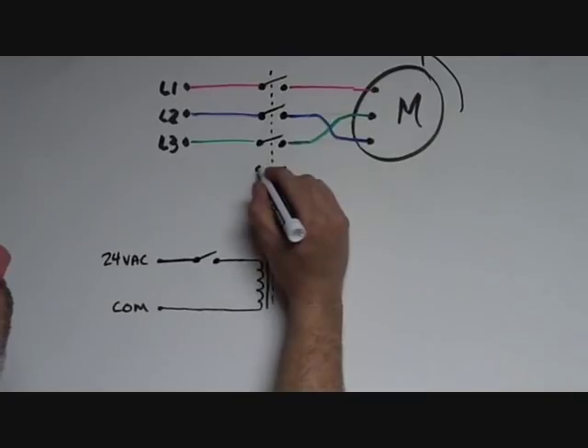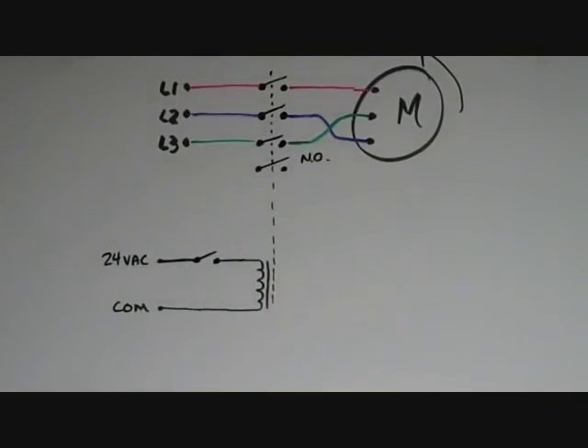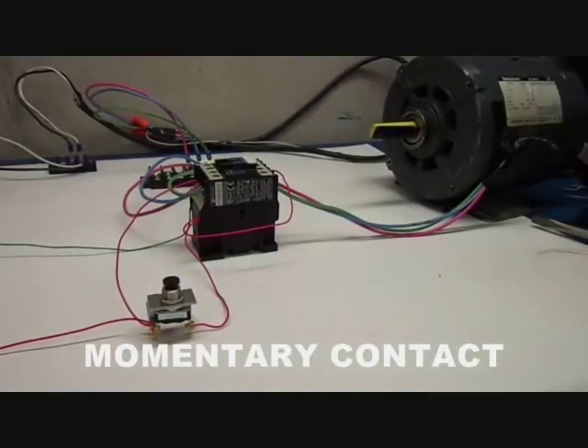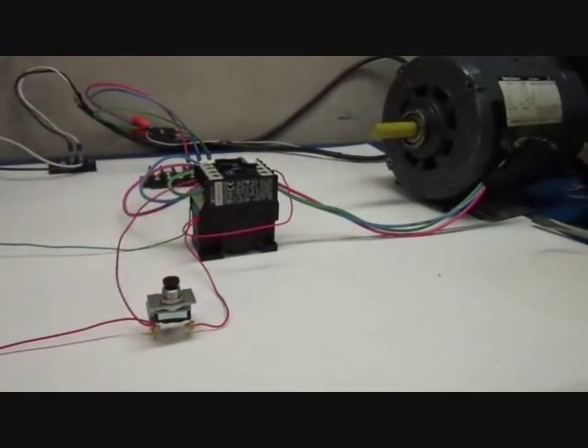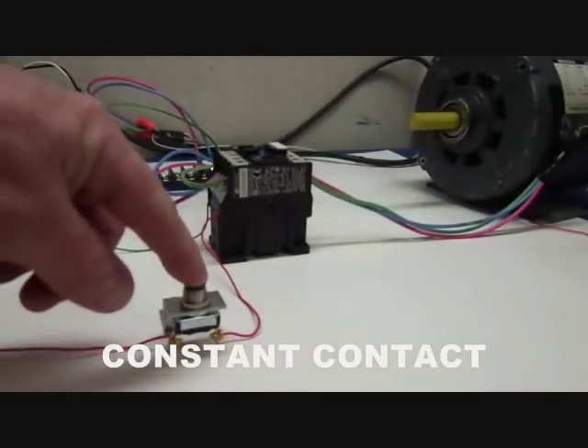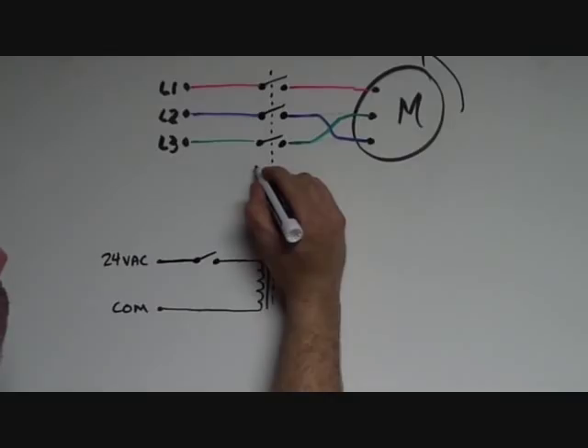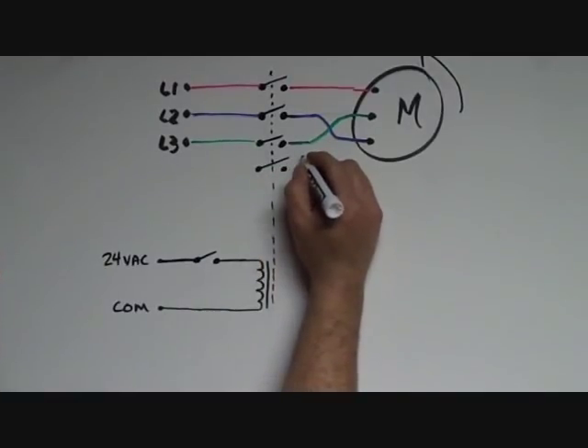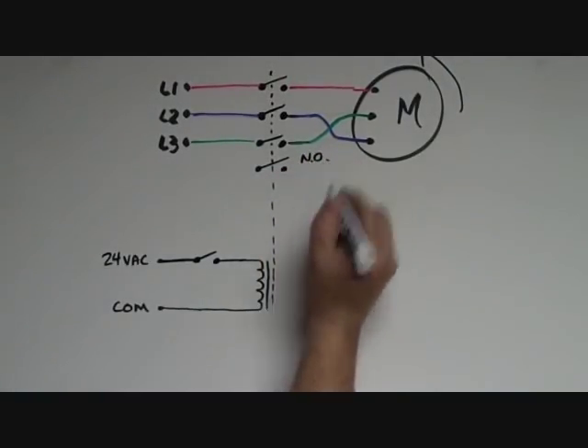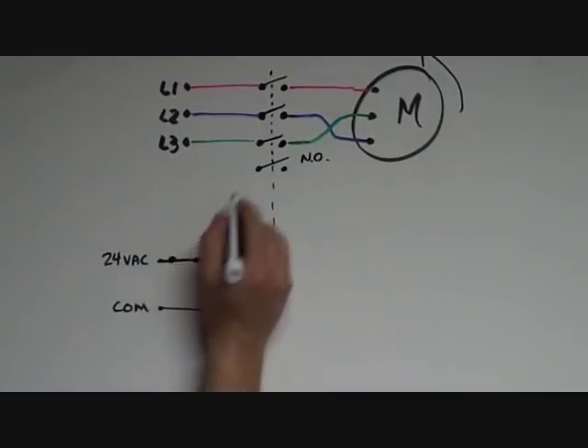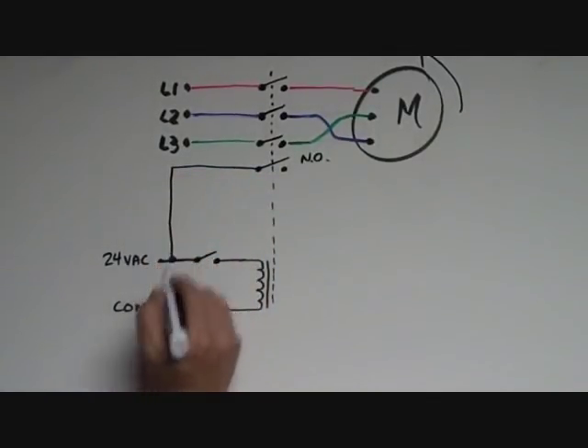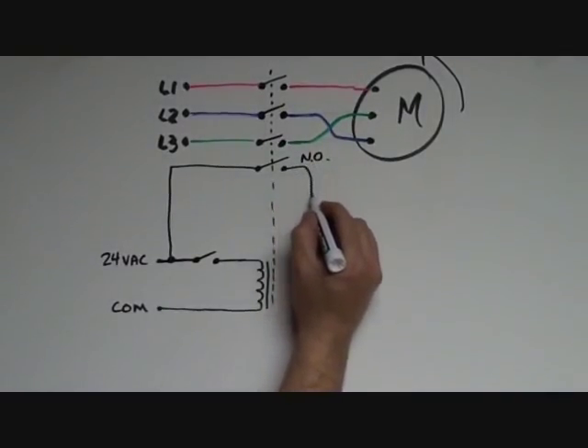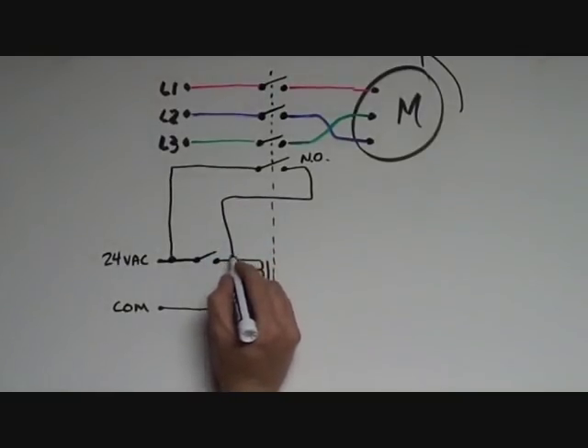That fourth set of contacts, the ones labeled normally open, are a lot of times used for continuous operation with only momentary contact of the push button. That means the contactor stays pulled in after you let go of the button or whatever. Constant contact means having to constantly hold in the button to keep the motor running. To switch over to momentary contact, I'm going to use that fourth set of contacts in parallel with the 24 volt push button to make that contactor function like a latching relay. I need a constant 24 volts to go into one of the normally open contacts, and I might as well get it from in front of the push button. Then I'm going to run a wire out of the normally open contact and to the A1 terminal of the coil, the same place the wire from the push button goes.